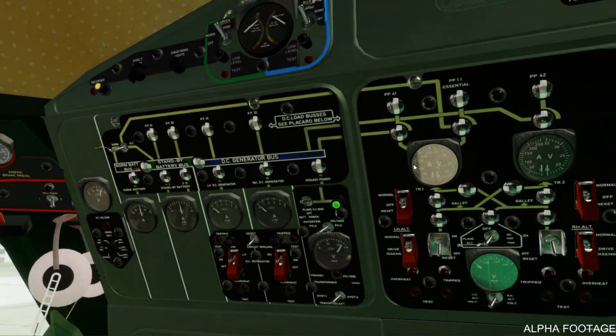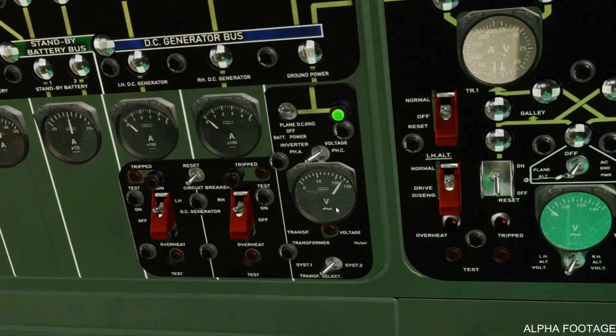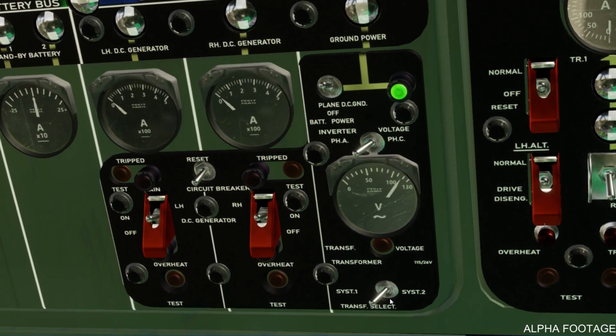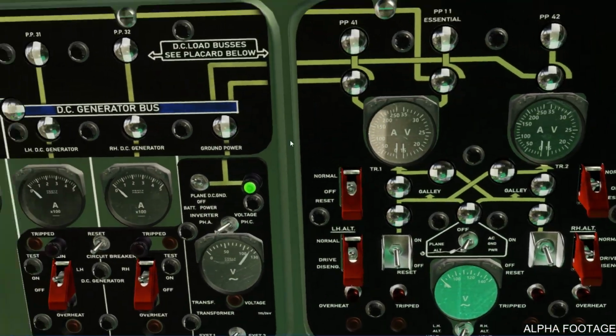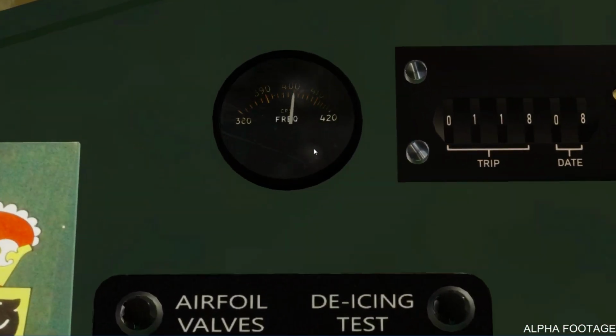So we go here to the engineer panel, we're going to check. This is approximately 115 volts, slightly over. We can check here phase A and phase C. And there's a note: the inverter voltage may exceed maximum limit during the initial operation, but should stabilize at normal values within some minutes. Furthermore, phase C voltage may be approximately 5 volts higher than phase A due to unequal load distribution. Use phase A for reference. And we check the frequency range is between 380 and 420 CPS.